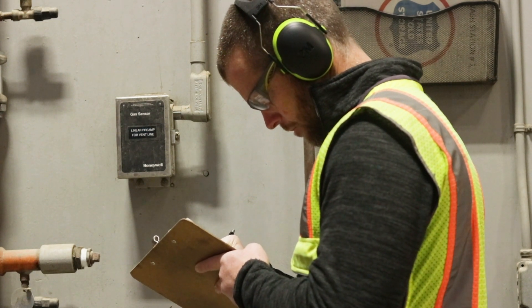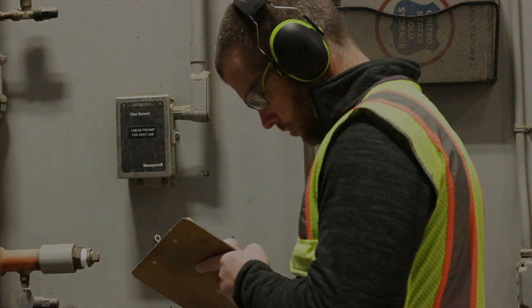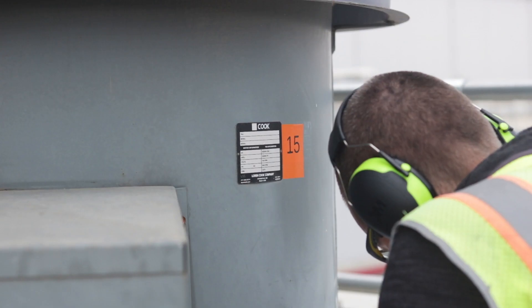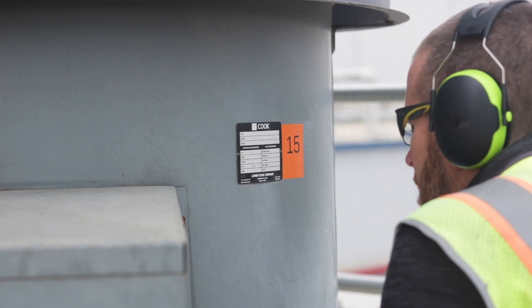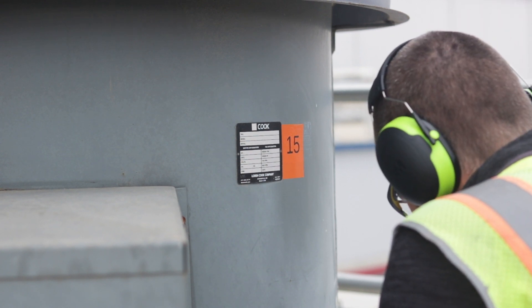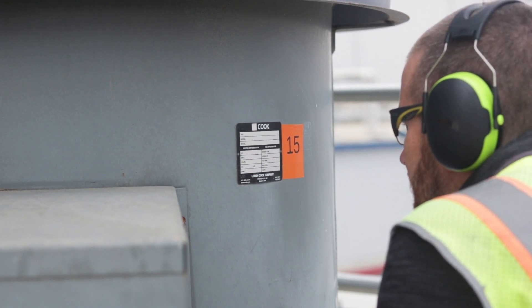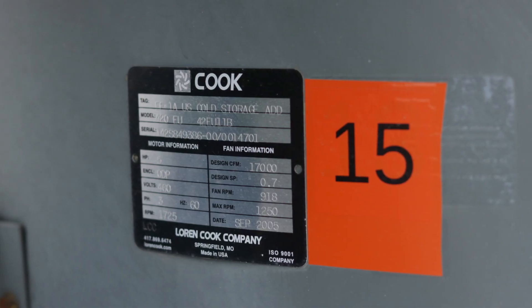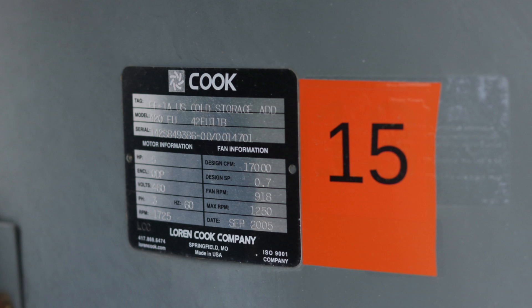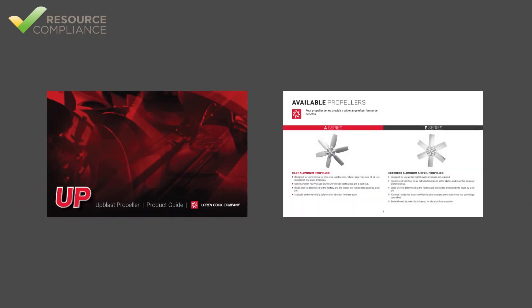Multiple pages can be used if necessary. The last section to complete before beginning the inspection checklist is entitled Machinery Room Ventilation System. The inspector must record the nameplate and airflow data for the fans that make up the Machinery Room Ventilation System. This emergency ventilation fan nameplate contains most of the information required on the form. The manufacturer literature was referenced to determine that the fan blades are aluminum.